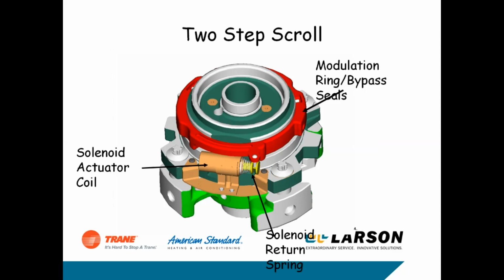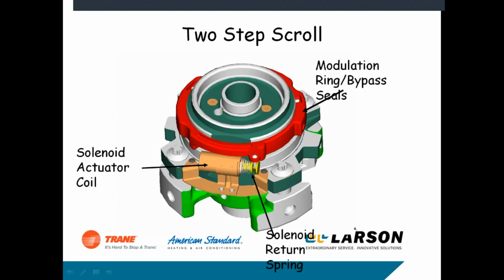All right, two-step scroll. It's a little different. It's got a unit on top of the compressor. It's got a little solenoid actuator in here. It's got a modulation bypass ring. Basically, when this solenoid is not energized, it bypasses refrigerant back into the shell of the compressor, about 20%. And when it energizes, it slides this scroll plate ring just slightly, misaligns these bypass holes, and it pumps 100% into the system.